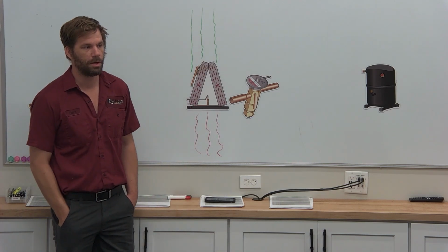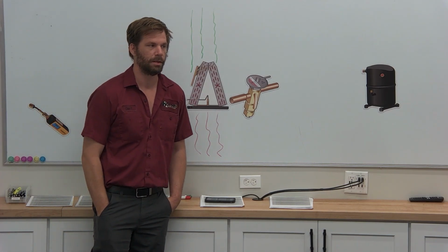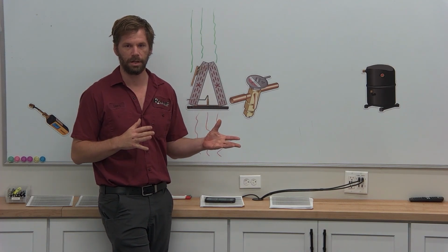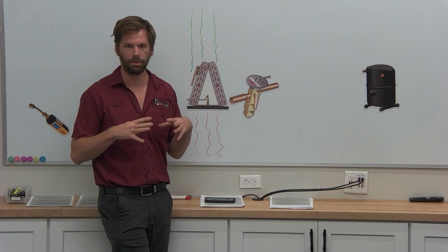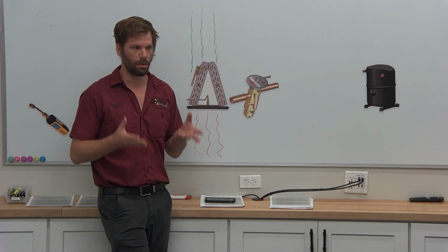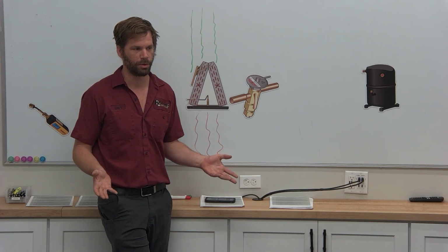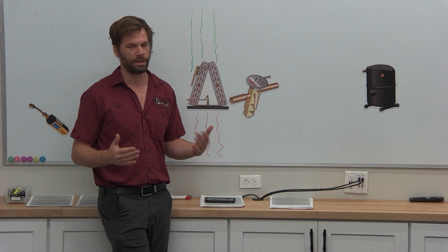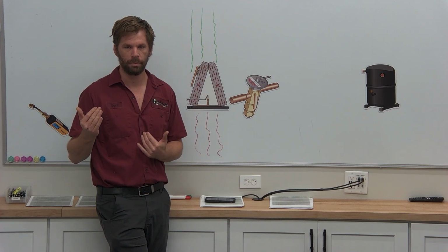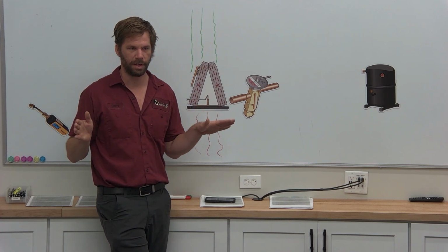So when you go to adjust the blower speed to try to change split, which means you're going to focus more on dehumidification, you're going to make that coil colder. You're going to let the air pass a little slower across the coil and drop off more moisture. You need to make sure it's a situation where the AC is actually keeping up in the home and it's hitting temperature just fine.